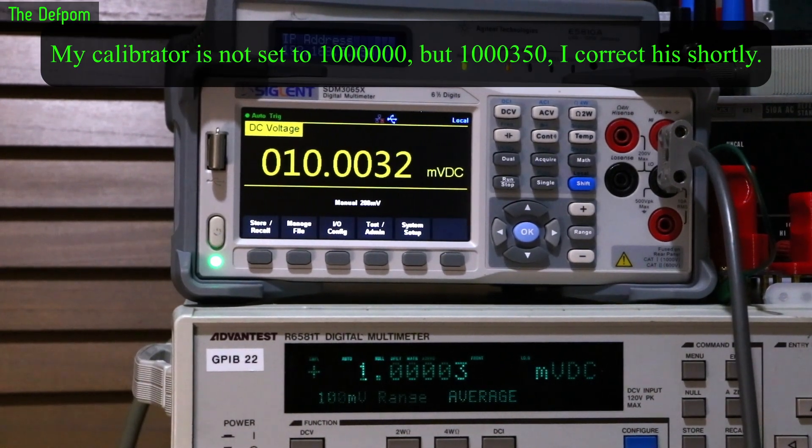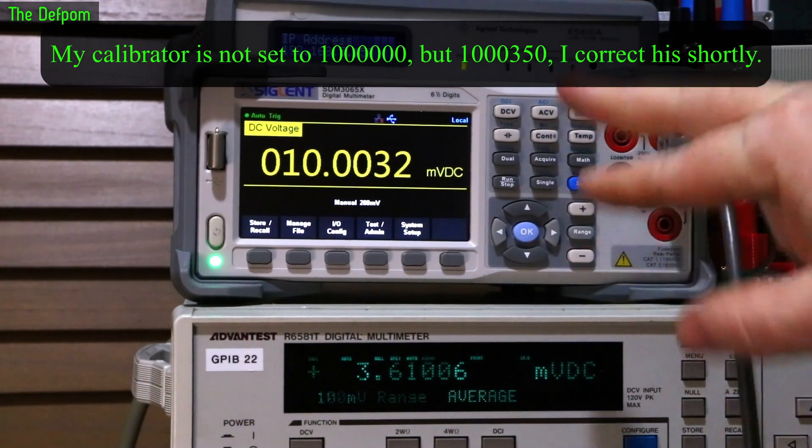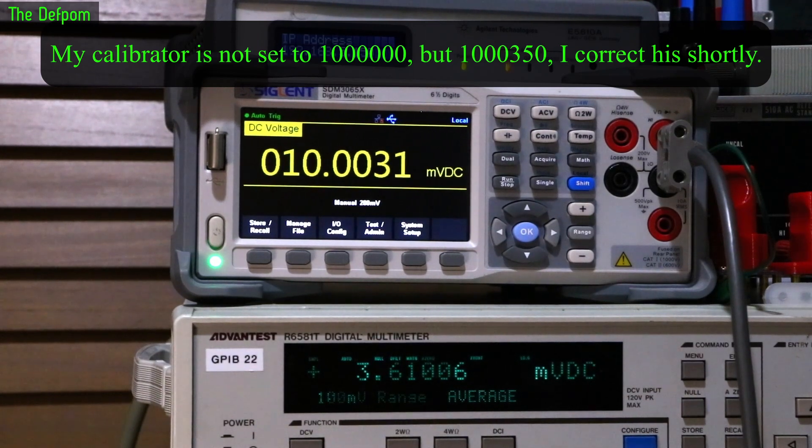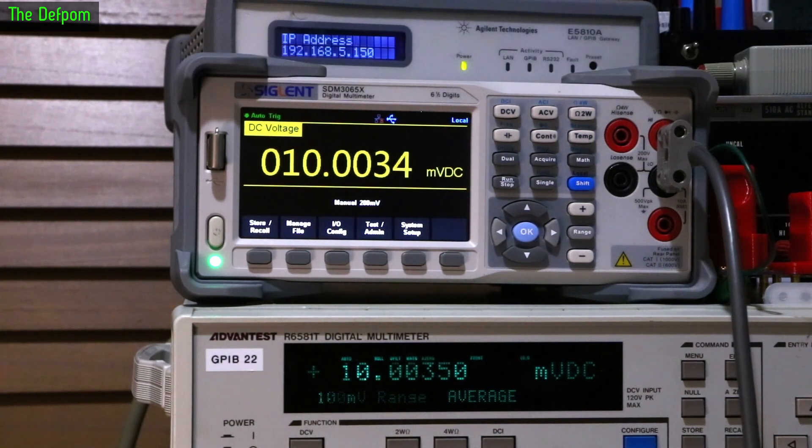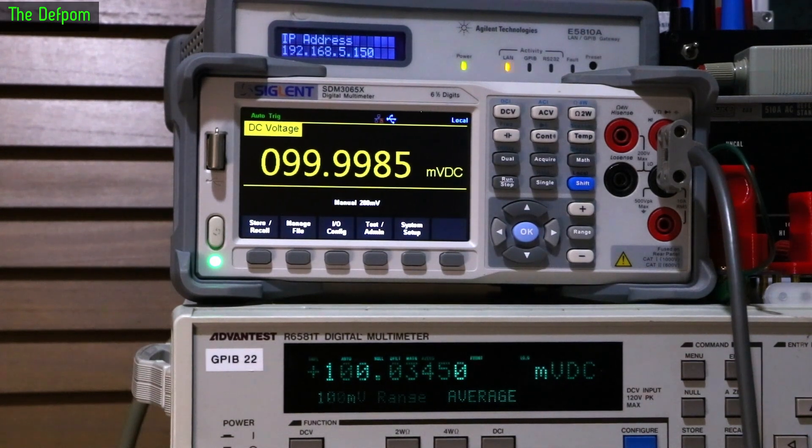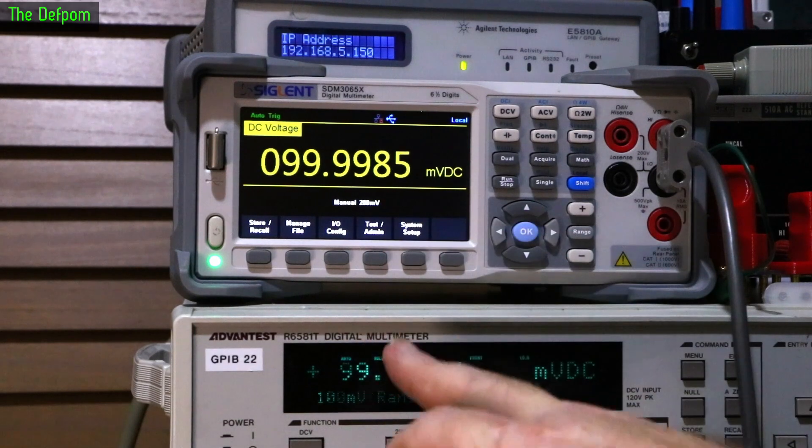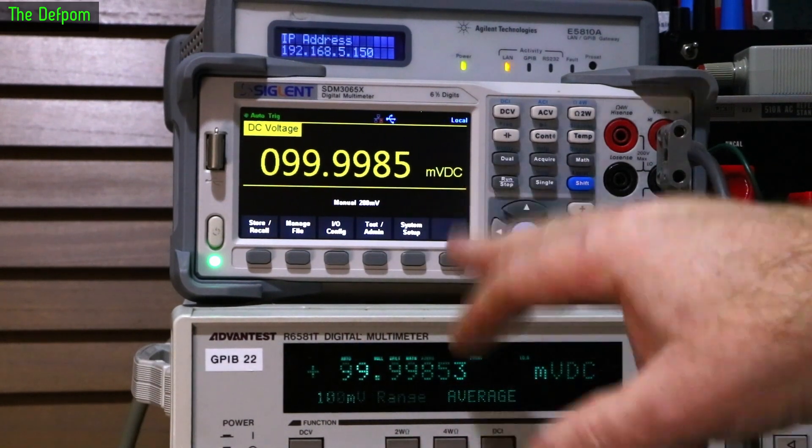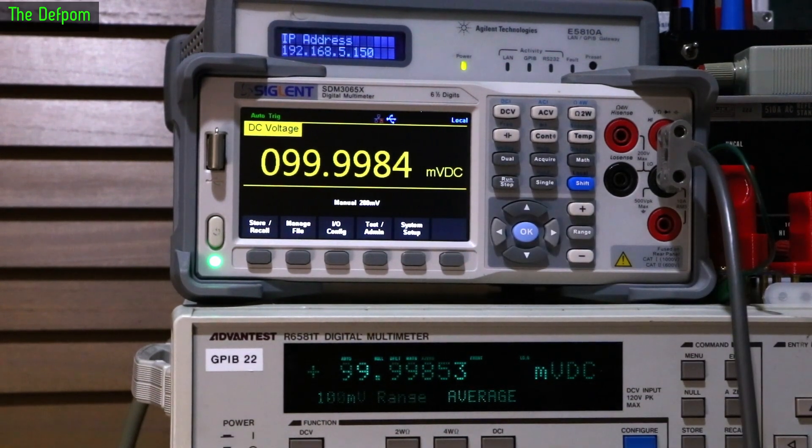There's a bit of noise which is affecting these readings slightly. But that's one millivolt. Just do 10 millivolt output on the calibrator. These things should basically match. They do. Look at that, it's pretty close. Again noise is playing a bit of a factor. So 100 millivolt, calibrating to nice rounded numbers. There we go, 9984 or so. Jumping around a bit of noise. That's looking right.